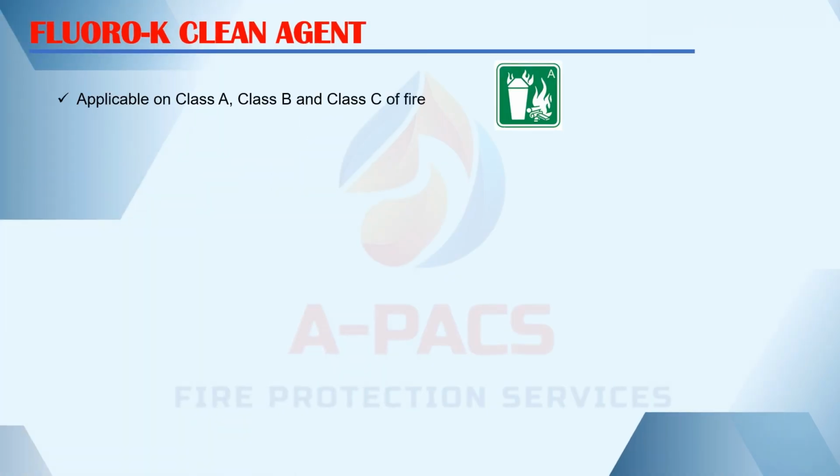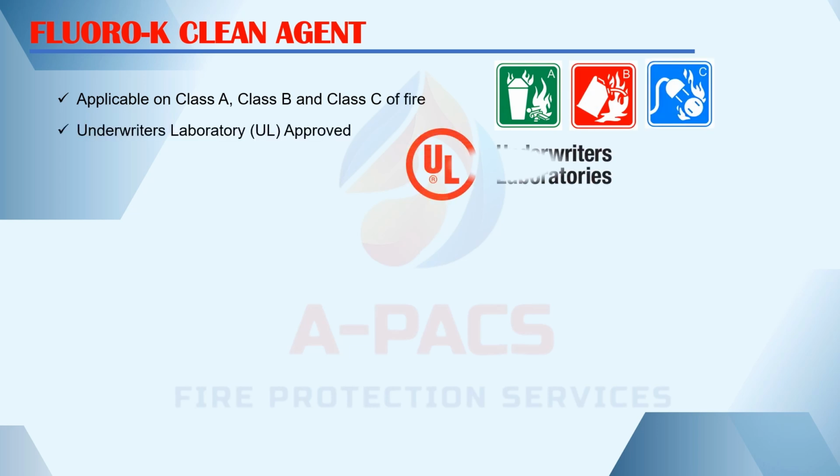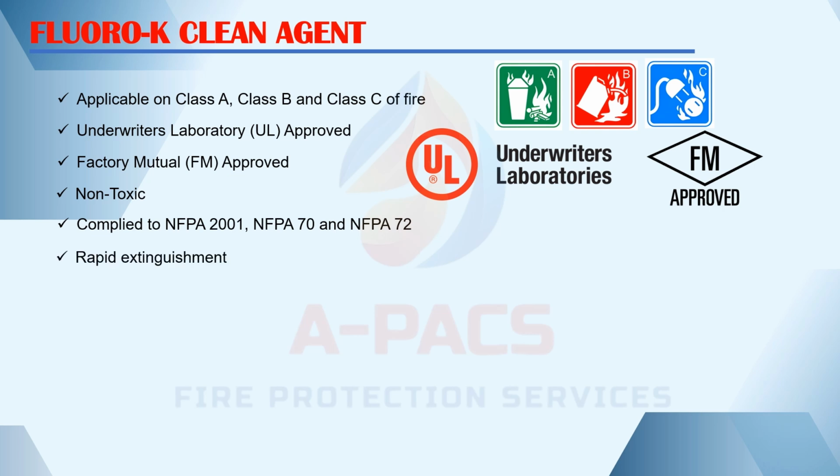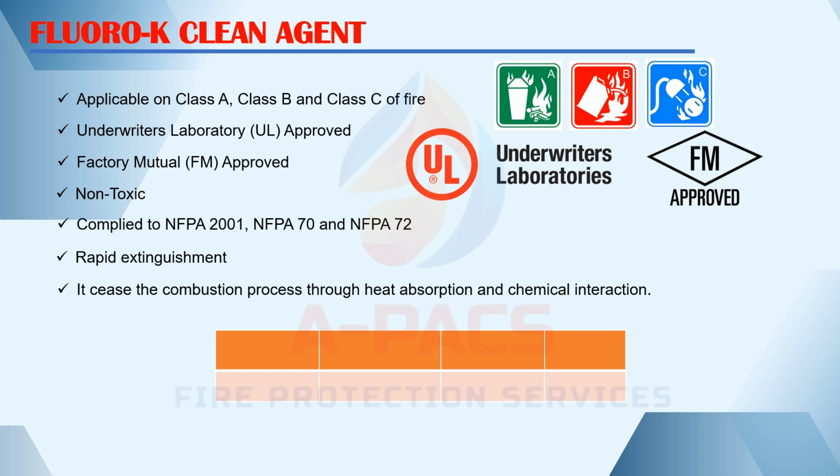Applicable on Class A, Class B and Class C fires. Underwriters Laboratory, UL, approved. Factory Mutual, FM, approved. And non-toxic. Complies with NFPA 2001, NFPA 70 and NFPA 72. And rapid extinguishment: it ceases the combustion process through heat absorption and chemical interaction.